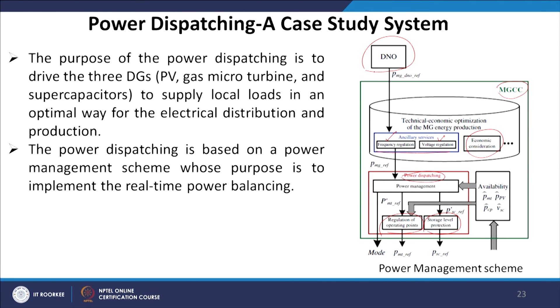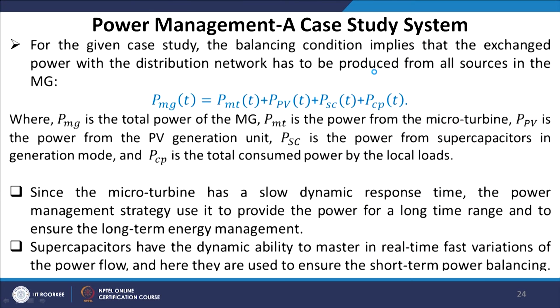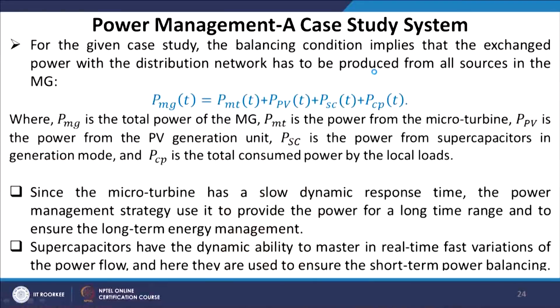The power dispatching is based on a power management scheme whose purpose is to implement real-time power balance. Before sending the dispatching power set-point to each unit, some protection and regulation strategies need to be added. The balancing condition implies that the exchange power with the distribution network must be produced from all sources in the microgrid. The total power PMG of the microgrid comes from the micro turbine, PV generation, super capacitor, as well as the total consumed or critical loads.